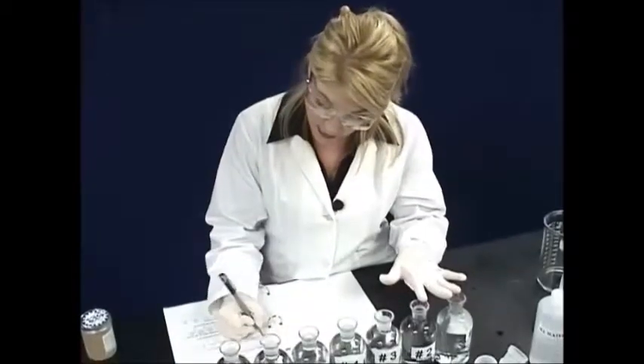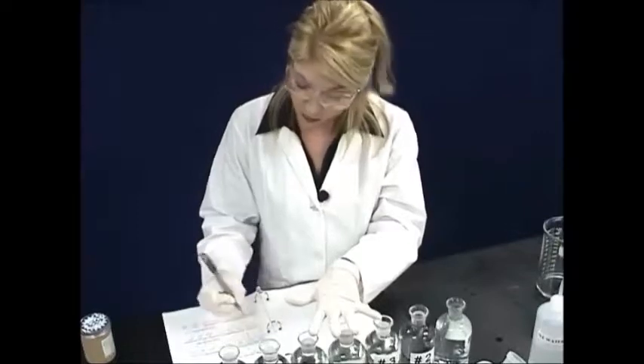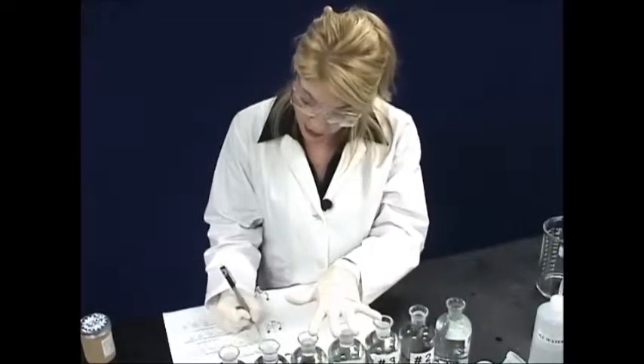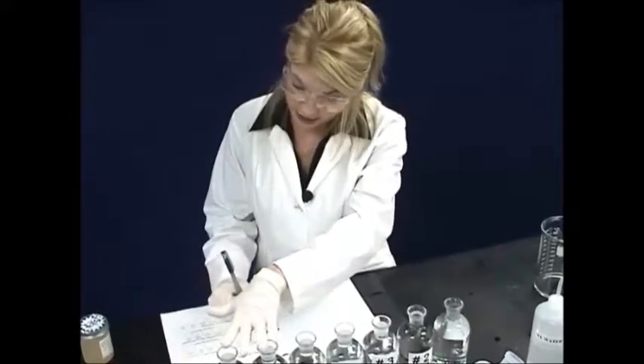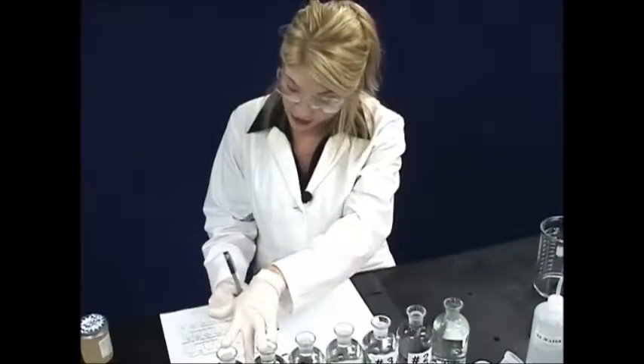Next, we will record the bottle numbers of the bottles that we're testing. I have bottles number 1 through 7, and I'm going to record bottles number 1 and 2 for our blanks. Our 3 bottles that determine the seed control factor, bottles number 3, 4, and 5. And finally, our 2 bottles that are our GGA standard checks, bottles number 6 and 7. You'll want to continue recording the numbers of all of the bottles that you have ready to be tested.